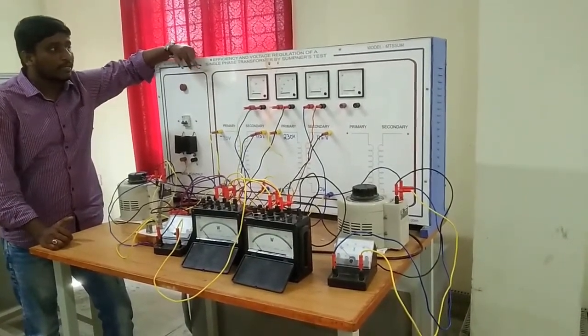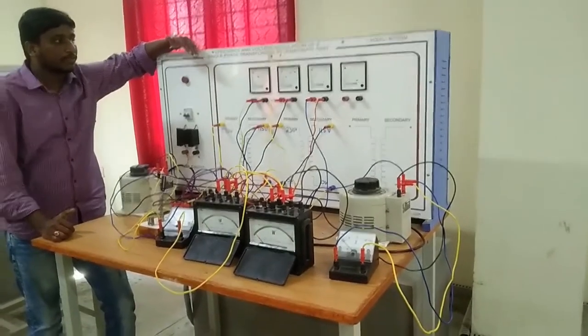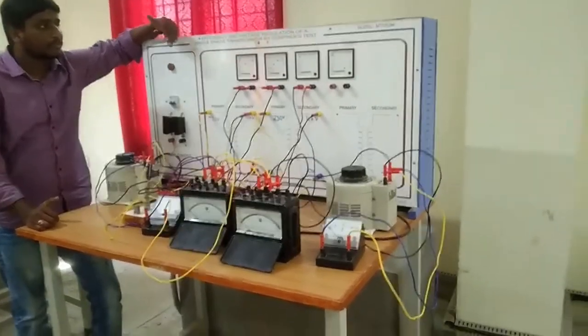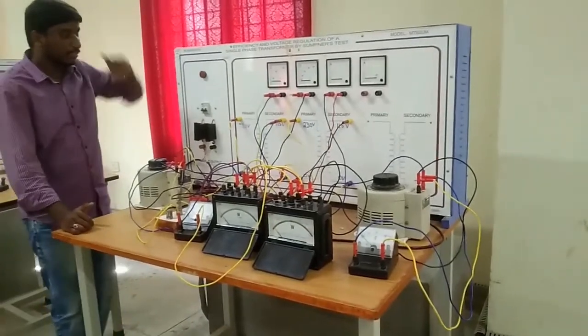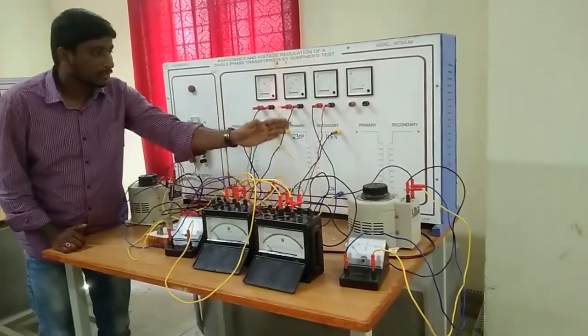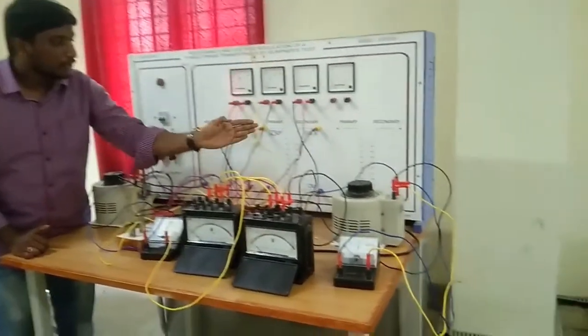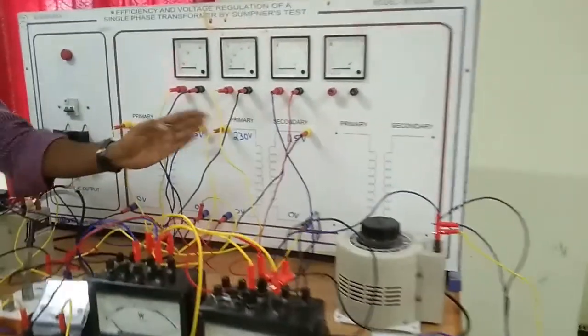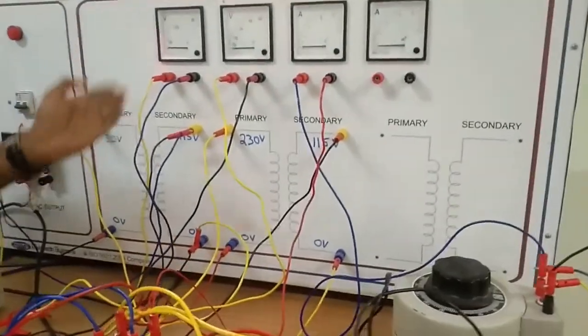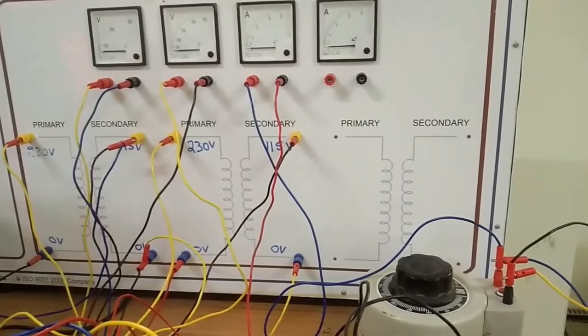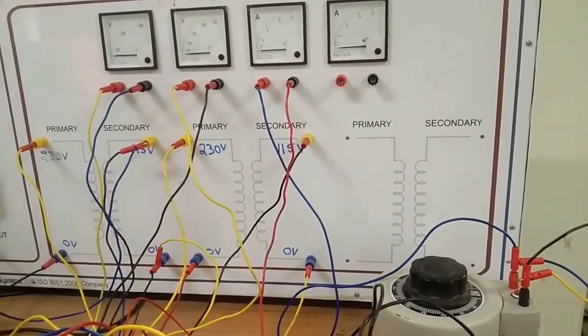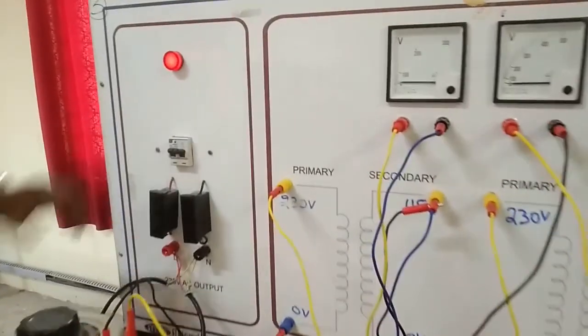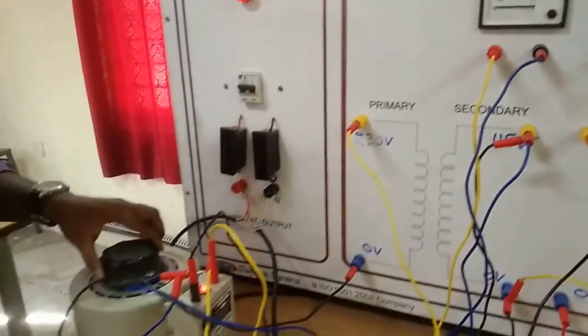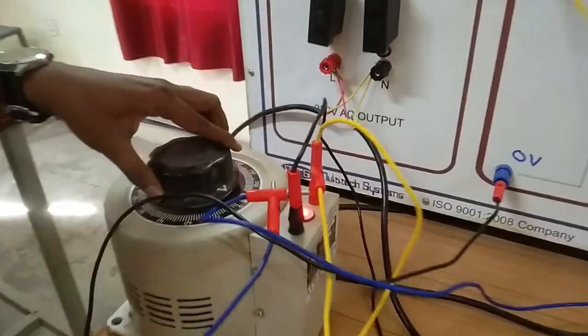If you want to find the efficiency of an individual transformer at a time, we need to perform the Sumpner test. So here we are taking two transformers, and the two primaries are connected in parallel as well as the two secondaries are connected in series opposition. So here I am going to perform the Sumpner test. I am simply turning the MCB on. With the help of this auto transformer, I am applying supply to the primaries of both the transformers, right?